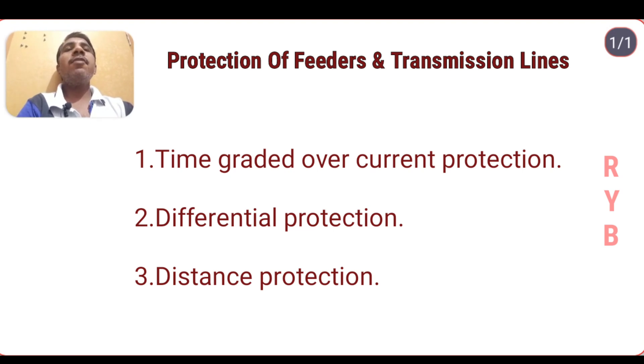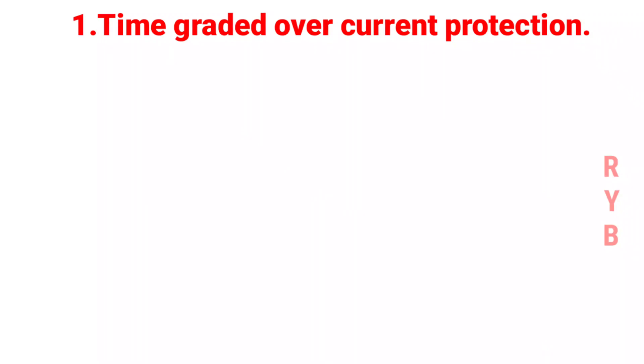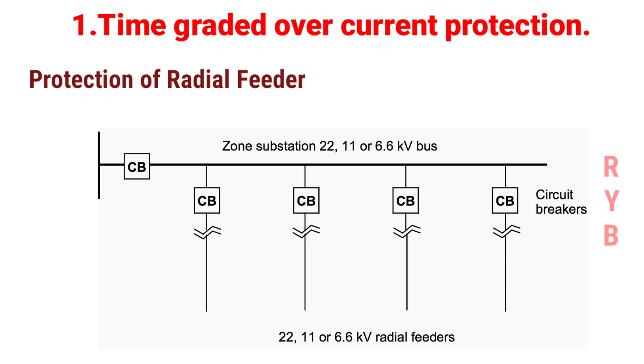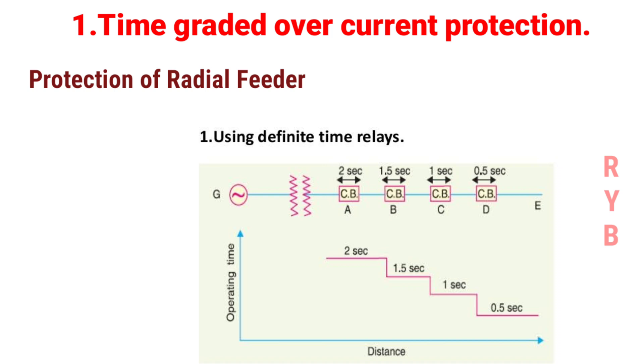Let us go for time graded over-current protection, starting with protection of radial feeders. A radial feeder radiates from the substation in one direction only — power can flow in one direction only, from source to load. There are three types of feeders: radial, loop, and ring main. A radial feeder can be easily protected by using either definite time relays or inverse time relays.